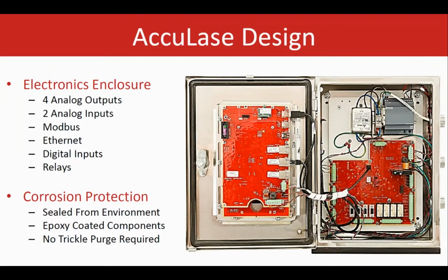So for the 20 milliamp analog outputs, discrete inputs, as well as the dry contact relays for the concentration and fault alarms, Ethernet for the Modbus TCP/IP, Ethernet for the remote GUI, Modbus RS-485, RS-232. These are all part of what AccuLase can offer. The system is sealed from the environment for corrosion protection and uses epoxy-coated components. Also, there is no trickle purge requirement, which is a great advantage to have on these units.